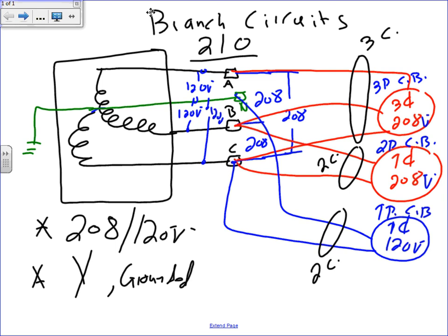Because if not, you know what not grouping is? Not grouping is having one conduit for these three conductors, another conduit for these two conductors, and a third conduit for these two conductors. Are you kidding me? The smallest conduit EMT you can buy is half an inch. So depending on the size, you've got yourself a minimum of three conduits, half an inch each. Could I put the three of them in one 3/4 inch conduit and save myself a lot of money? Yes, and that's exactly what we do.